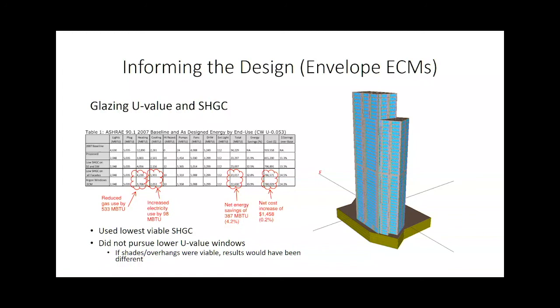But as often happens with lower U-value windows, we actually increased the cooling energy by 98 MBTUs per year. This generally happens because with more insulative windows, you're creating more of a thermos, more of a greenhouse effect, where at times when the inside of the building is warmer than the outside atmosphere, if the windows are not very insulative, you can just conductively lose that heat to the outside, and that actually reduces your cooling energy or your cooling requirements.